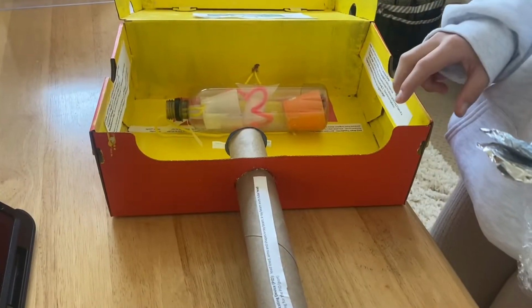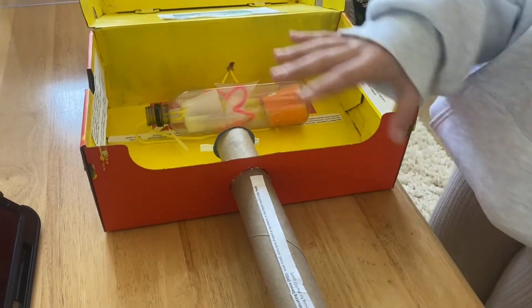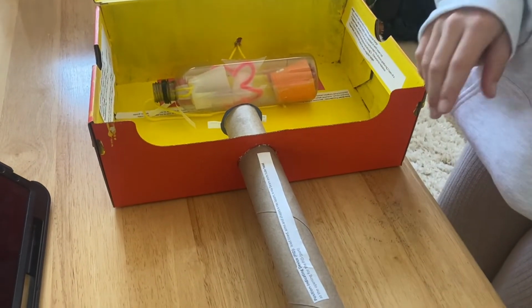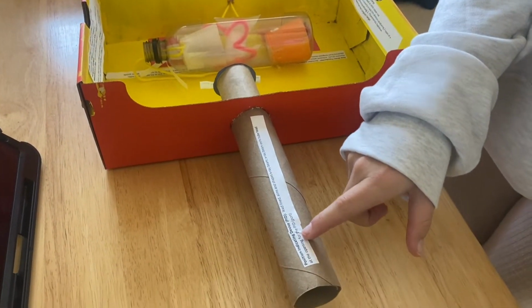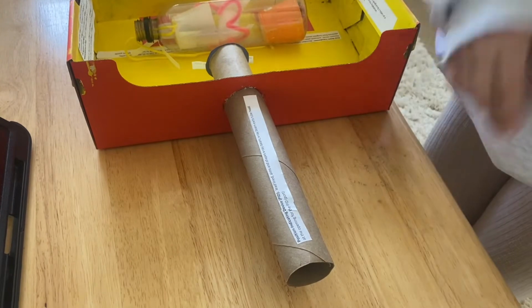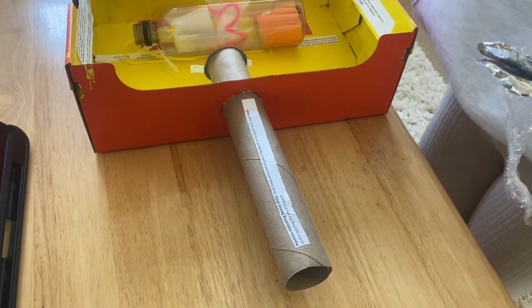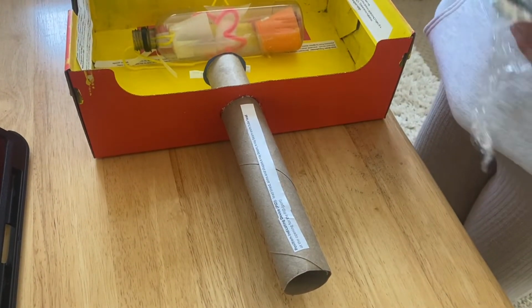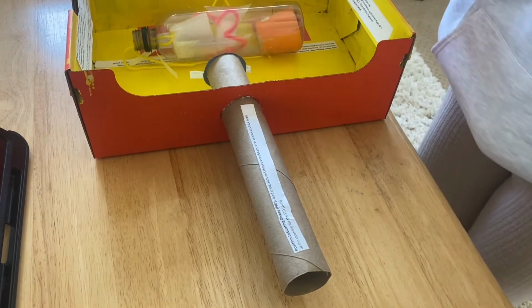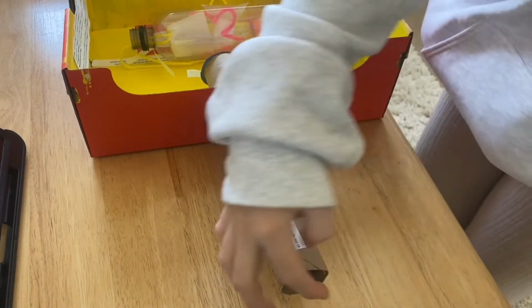So now I'll just explain parts of this operation that I didn't go over when explaining how X-rays are produced. Here we've got the position indicating device, the PID. It's lead lined and it aims and shapes the X-ray beam, and the X-ray beam will actually exit the tube head at the opening of the PID port, and this would be the PID port.